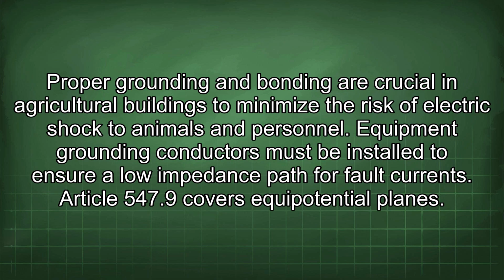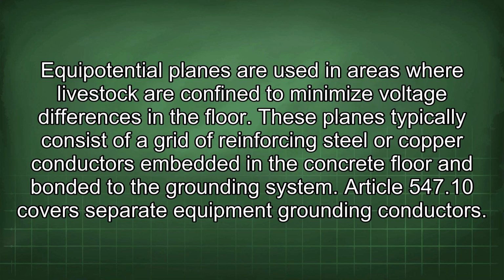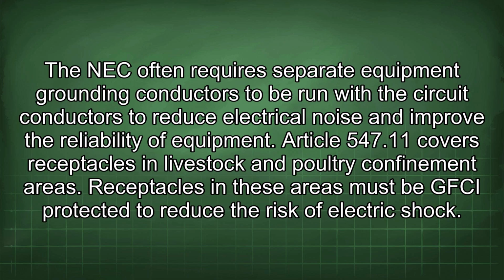Article 547.9 covers equipotential planes. Equipotential planes are used in areas where livestock are confined to minimize voltage differences in the floor. These planes typically consist of a grid of reinforcing steel or copper conductors embedded in the concrete floor and bonded to the grounding system. Article 547.10 covers separate equipment grounding conductors. The NEC often requires separate equipment grounding conductors to be run with the circuit conductors to reduce electrical noise and improve the reliability of equipment.